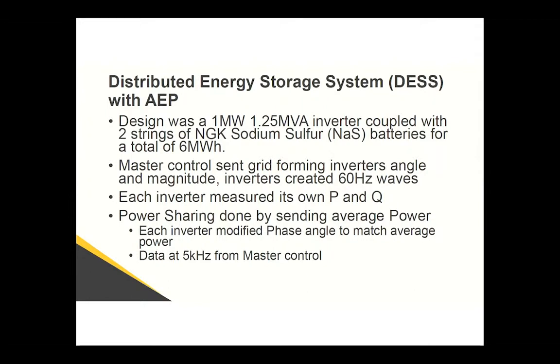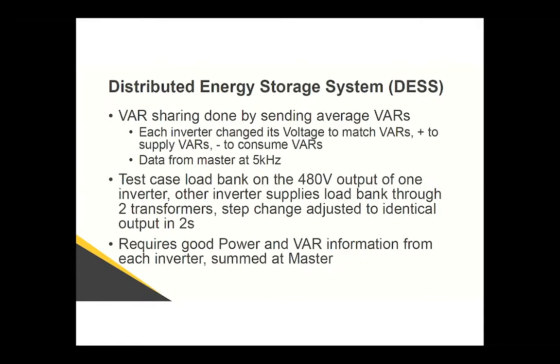So in this case, the master control would send an angle and a voltage for the various inverters to run at. And to get sharing, what we did was we would measure at each inverter the power and the VARs, sum them up, send the average back, and then for sharing power, we change the phase angle to get the power to be the average power, and to share VARs, we change the voltage in order to get the voltage sharing. That was done with data that was running at about 5 kilohertz out to our master control and back. So still highly communication dependent.